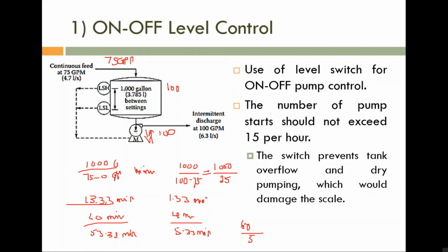Normally we are operating a centrifugal pump, we are starting it, and we are stopping it. If you are starting a centrifugal pump, it has to overcome the starting friction, Coulomb friction. Starting friction is more means more heat energy is developed. So if the number of starts is more, the heat energy generated is also very large. Means power dissipation, energy dissipation is also very large.